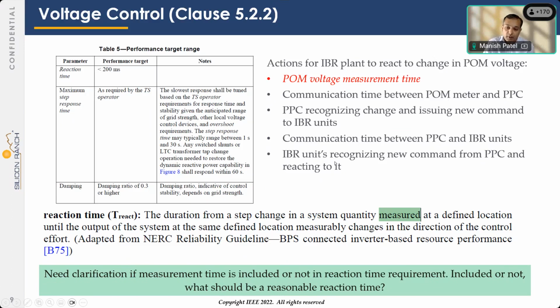right? One more caveat, if you go and look at the reaction time definition itself in the standard, it says the duration from a step change in system quantity measured. I highlight the word measured. So does that mean that the time that the meter at the POM takes to measure the voltage is not part of this reaction time? I don't know what the right or wrong answer is, or I don't want to imply that I know the right or the wrong answer, but I think there is an opportunity to clarify all this. All I could say is that it is my recollection that when the 200 millisecond number was agreed upon within the working group, it included the measurement time for POM voltage.